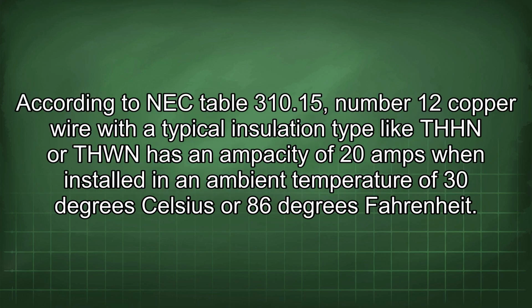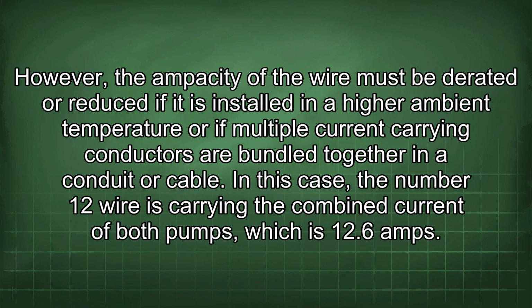According to NEC Table 310.15, number 12 copper wire with a typical insulation type like THHN or THWN has an ampacity of 20 amps when installed in an ambient temperature of 30 degrees Celsius or 86 degrees Fahrenheit. However, the ampacity of the wire must be derated or reduced if it is installed in a higher ambient temperature or if multiple current-carrying conductors are bundled together in a conduit or cable. In this case, the number 12 wire is carrying the combined current of both pumps, which is 12.6 amps.